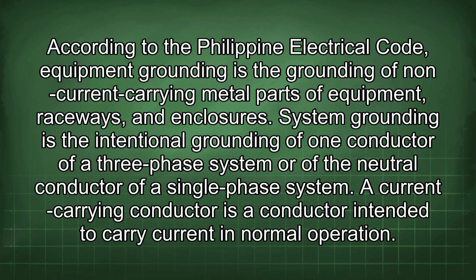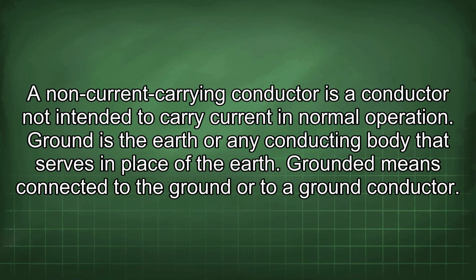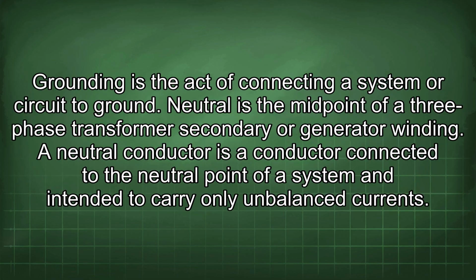According to the Philippine Electrical Code, equipment grounding is the grounding of non-current carrying metal parts of equipment, raceways, and enclosures. System grounding is the intentional grounding of one conductor of a three-phase system or of the neutral conductor of a single-phase system. A current-carrying conductor is a conductor intended to carry current in normal operation. A non-current carrying conductor is a conductor not intended to carry current in normal operation. Ground is the earth or any conducting body that serves in place of the earth. Grounded means connected to the ground or to a ground conductor. Grounding is the act of connecting a system or circuit to ground.